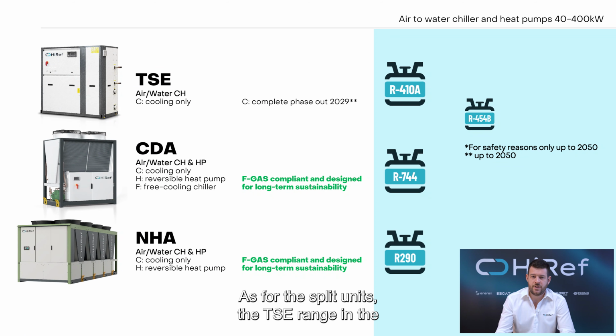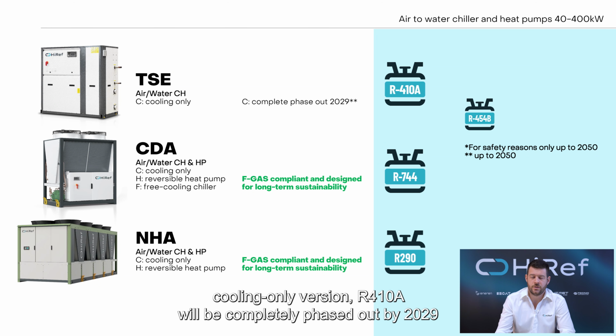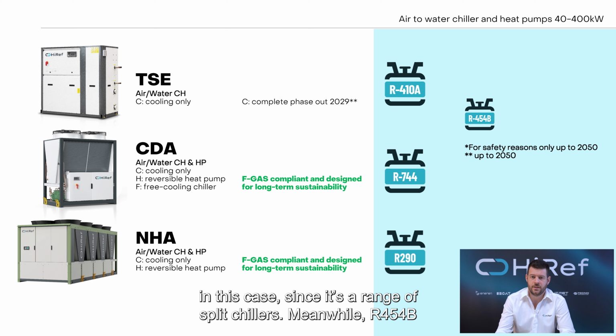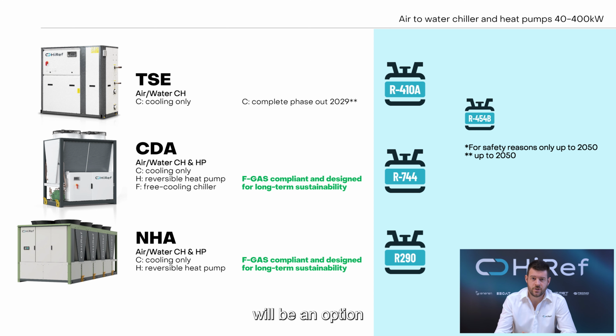As for the split units, the TSE range in the cooling only version, 410A will be completely phased out by 2029. In this case, since it's a range of split chillers, 454B will be an option available until 2050 without any restriction.